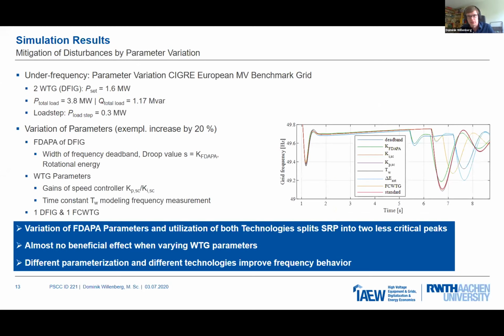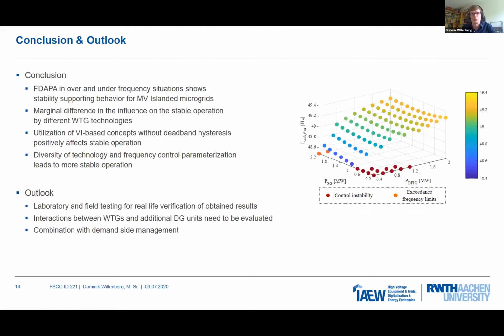Yes, definitely there is. Maybe I'll just go back to this slide. This is actually also something we investigated, of course, here just exemplarily. What we see here is, on the z-axis, the first frequency peak that occurs. On the bottom axis on the left side, the active power infeed of the synchronous generator, and on the right side, the active power infeed by a DFIG in that case. What we see is that, for example, in case of really small infeed of the synchronous generator or the CHP, we have control instabilities, which means that no steady state operation is possible, at least according to our simulations.